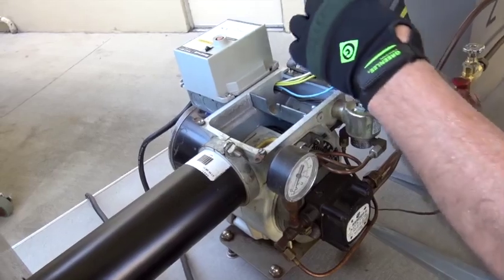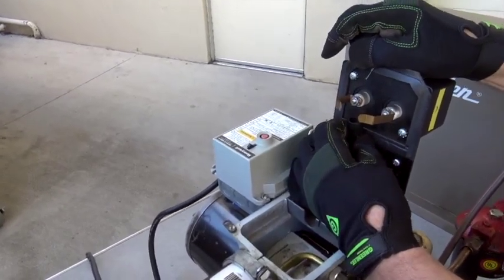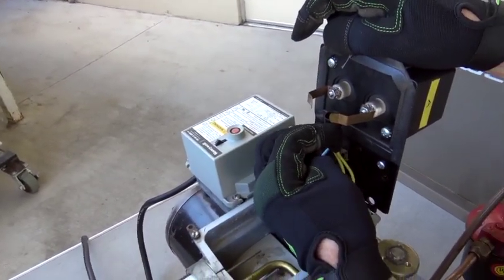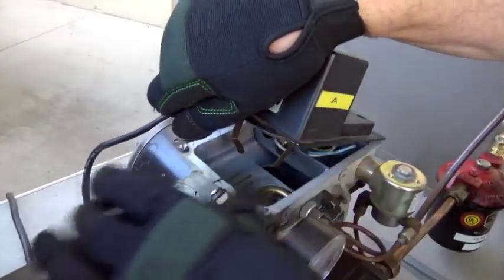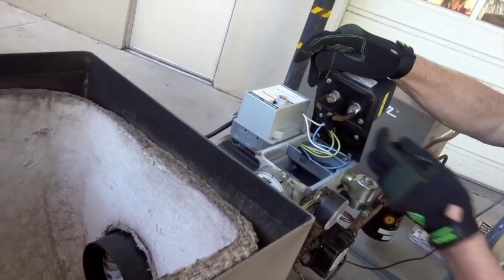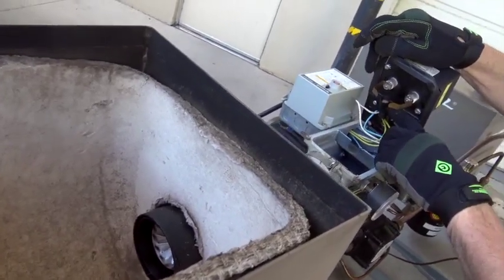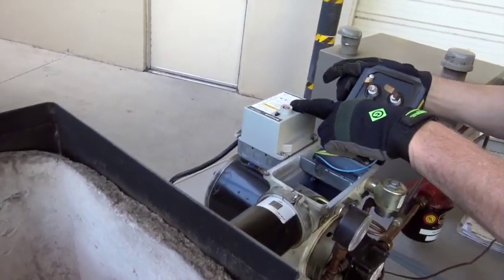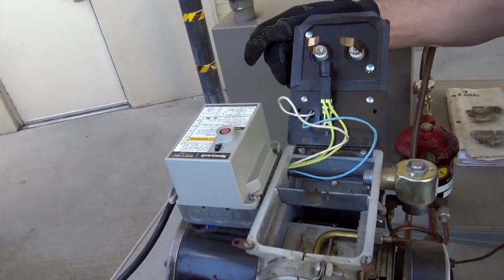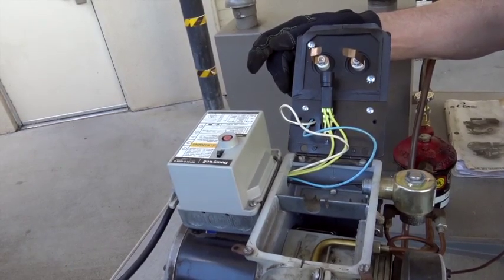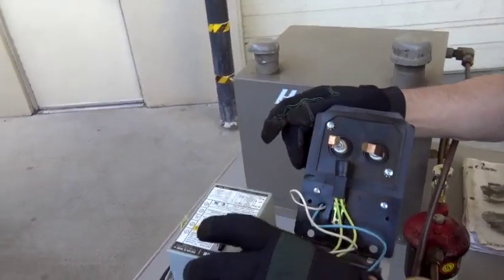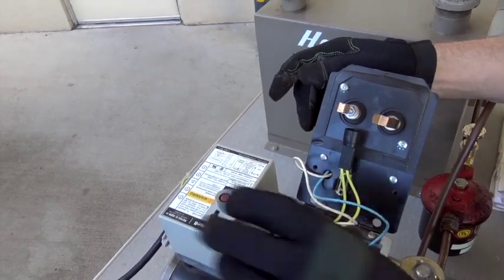We also have here a CAD cell, photosensitive cell. It's going to look downstream through that tube and pick up the burner light. If it doesn't see burner light through the photosensitive cell, it's going to send a signal here to this primary control to lock out. Now it's 45 seconds on trial for ignition. So let me tell you something. If it doesn't fire up and you reset this, every time you're dumping fuel into this pot.